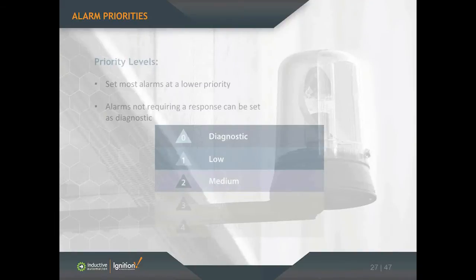The Alarm Management Handbook says that only 20% of your alarms in the system should be at a high or emergency level. So most of your alarms will probably be at that lower priority.